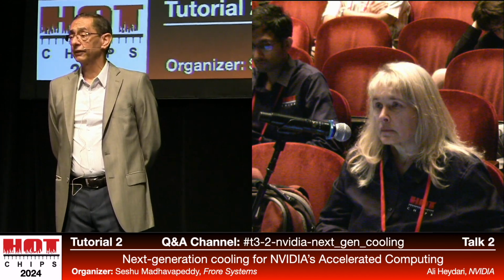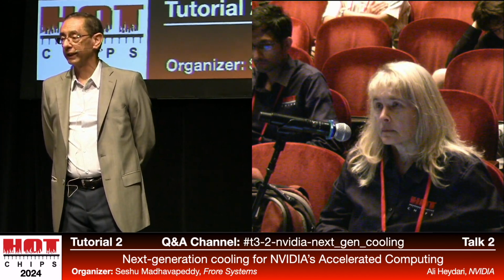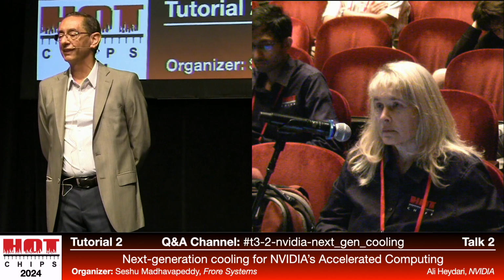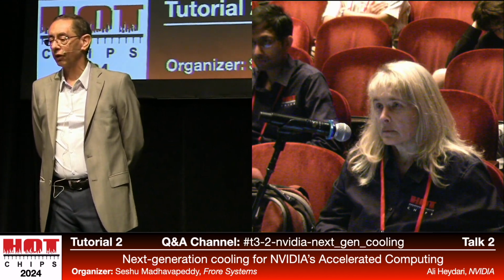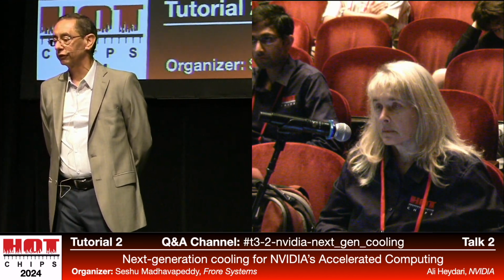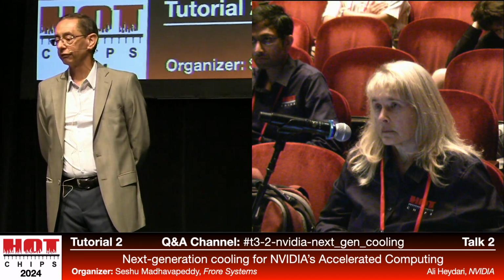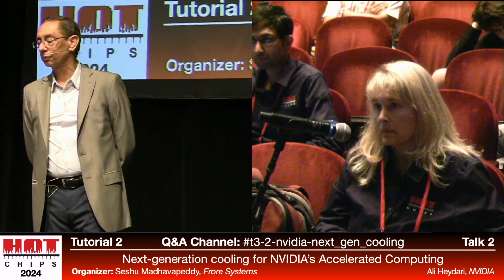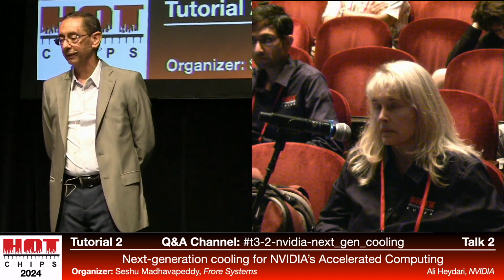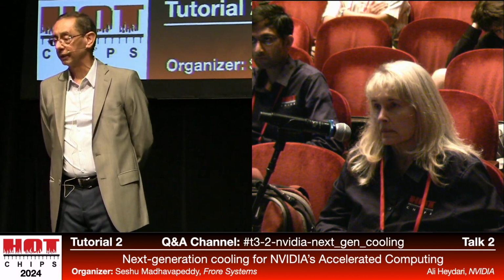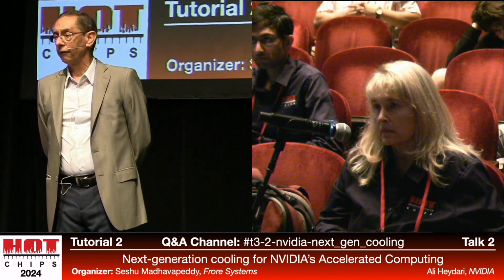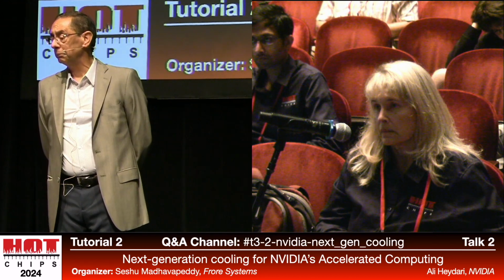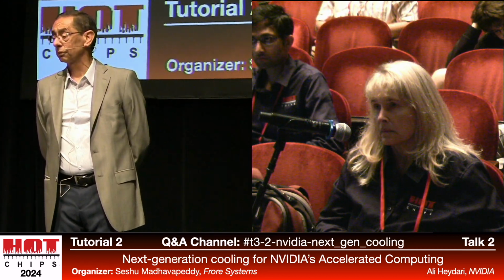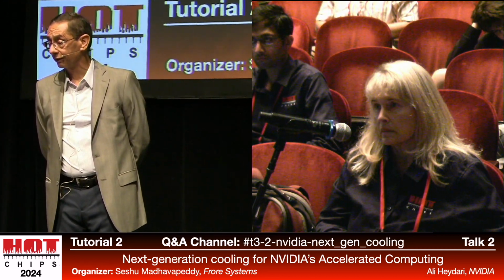Sure. I think, like air cooling, in my opinion the limit of single-phase liquid cooling is not going to be a limit of physics. In other words, I can always do air cooling of a chip at a kilowatt and above with fans and heat sinks - it just becomes impractical in action. Same with liquid cooling. I don't think I'll have a whole lot of problem cooling chips up to several kilowatts with single phase.